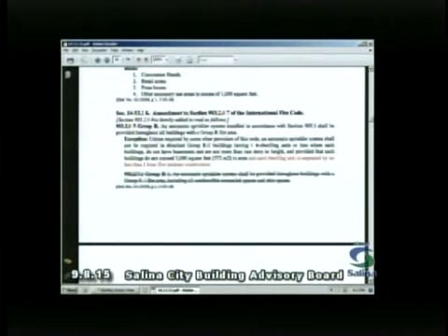However, when this was previously done, it was taken to the State Fire Marshal's office and obviously approved. And we are more restricted than what it was in the past, whereas 6 dwelling units or less, without basement, not more than 1 story in height, and provided such building not exceed 5,000 square feet, was an exemption to the sprinkler requirement. And now we have changed that to 4, and we've added the verbiage, and each dwelling unit is separated by no less than a 1-hour fire-resistant construction.